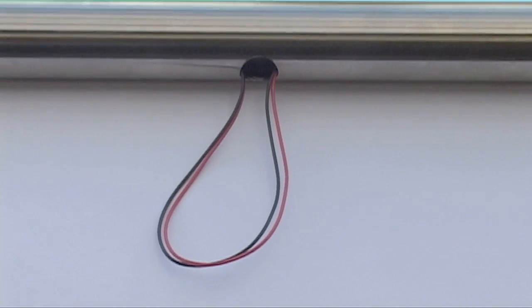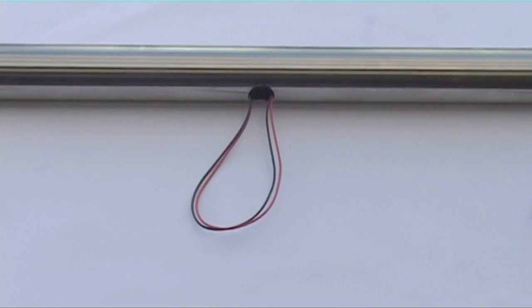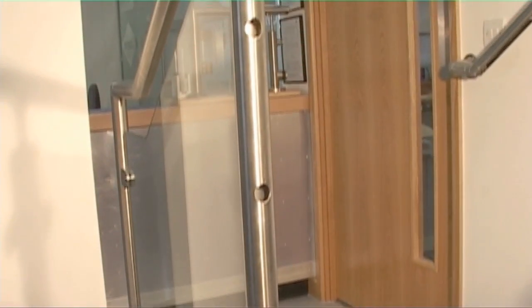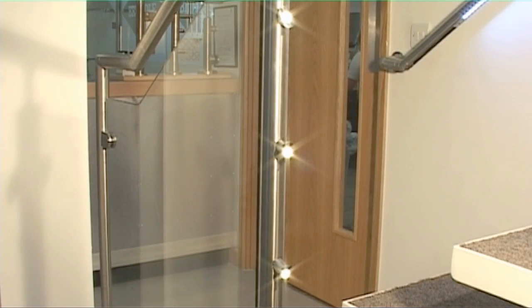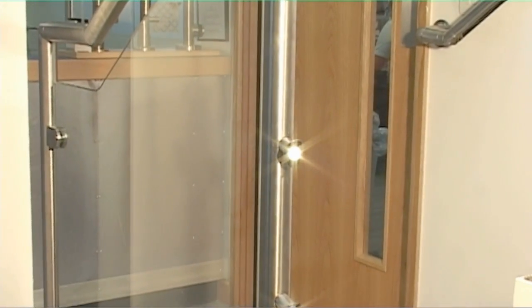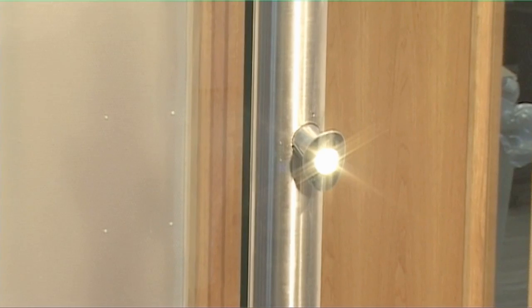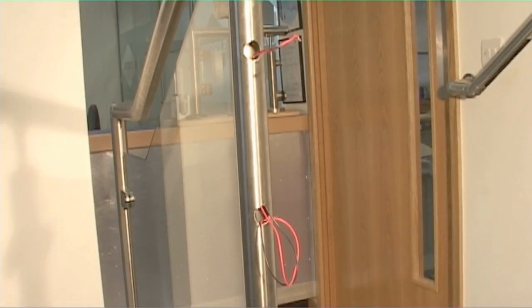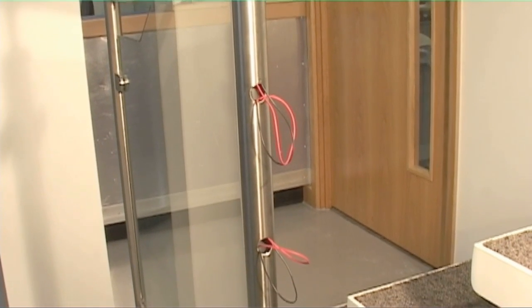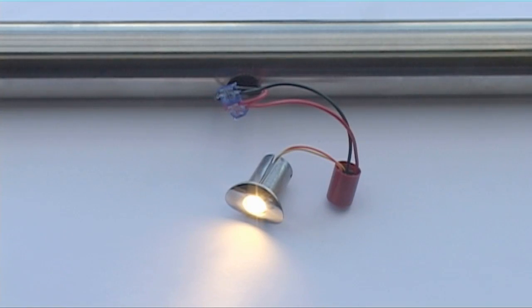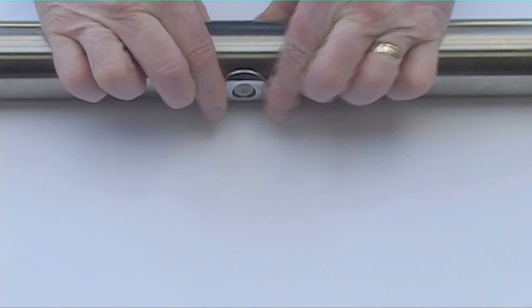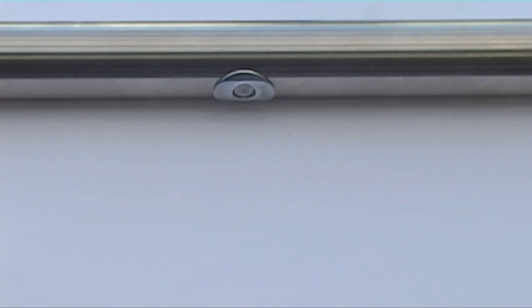When it comes to fitting the single lens LED pods, the cable is threaded through the handrail, which should have been pre-drilled with 24mm diameter holes at 300mm centres. The pods should not be inserted into the hole until all of the installation is tested. A small loop of connection cable should be pulled through the hole nearest to the transformer, and the first pod is fitted as described earlier. When all of the pods have been checked, they can be inserted into the tube, where they simply click into place. Extra holes can be drilled into the flange to locate 1 or 2 2mm rivets for extra security.